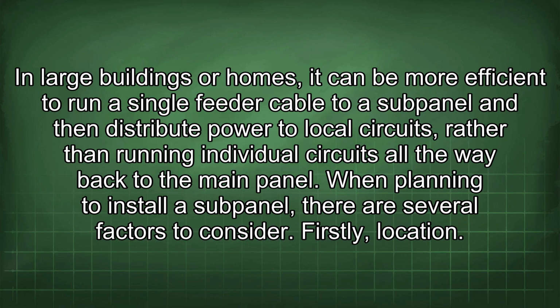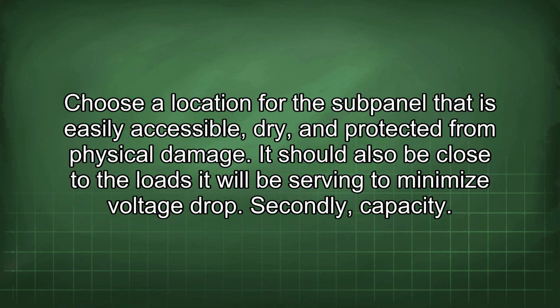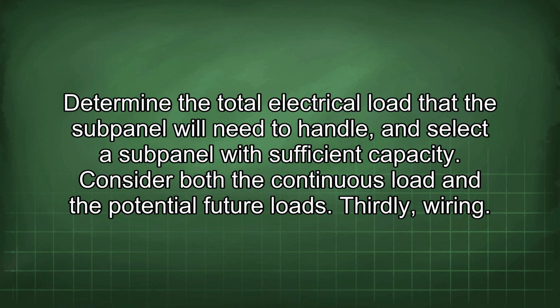Firstly, location. Choose a location for the subpanel that is easily accessible, dry, and protected from physical damage. It should also be close to the loads it will be serving to minimize voltage drop. Secondly, capacity. Determine the total electrical load that the subpanel will need to handle and select a subpanel with sufficient capacity.